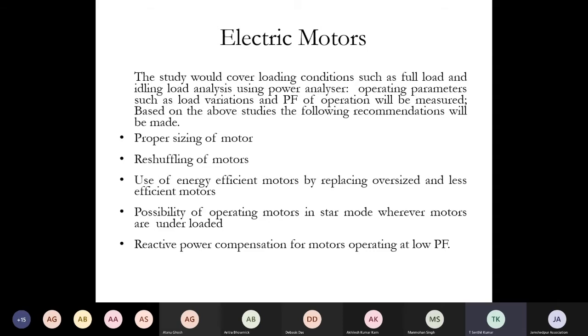The most important measure is the use of energy efficient motors. Now we have IE3 and IE4 motors, which are more energy efficient than standard motors by 5 to 6%. Several financial models are available to switch from standard motors to energy efficient motors, giving around 5 to 6% improvement in energy efficiency. Reactive power compensation on large motors is also possible, which gives a good improvement in power factor and thereby energy savings.